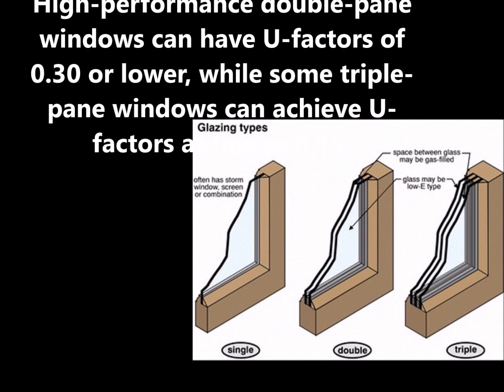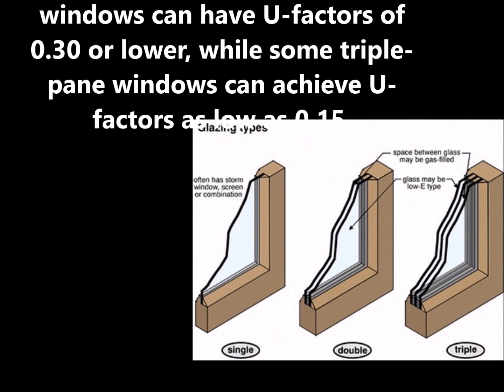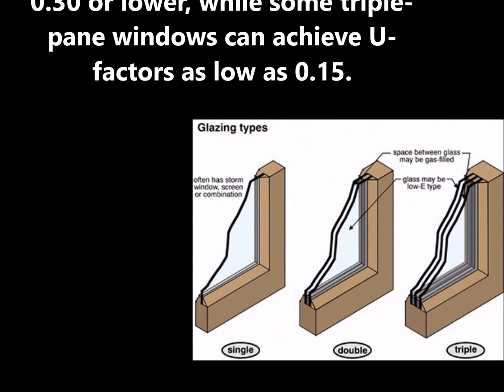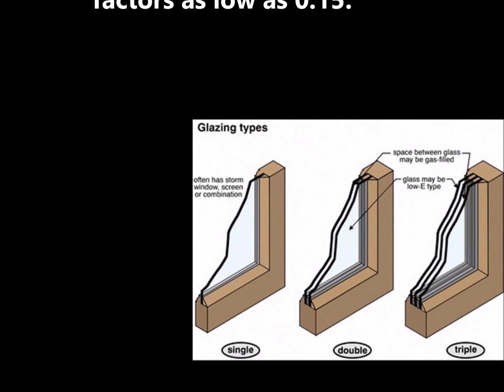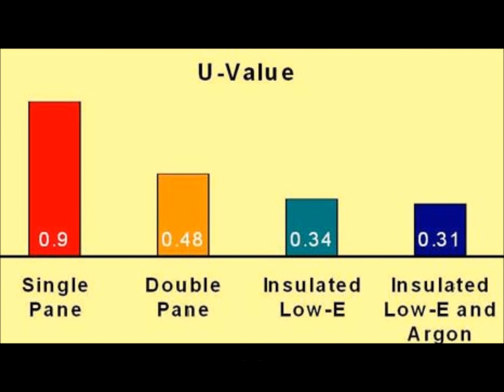High performance double pane windows can have U-Factors of 0.30 or lower, while some triple pane windows can achieve U-Factors as low as 0.15. Low U-Factors are most important in heating dominated climates, although they are also beneficial in cooling dominated climates. Energy Star provides recommended U-Factors for your climate. Additionally, the window selection tool compares average simulated energy costs for your location based on various window types. We've included a sample of how to input the data for your location as well as a resulting report in the course following this video component.